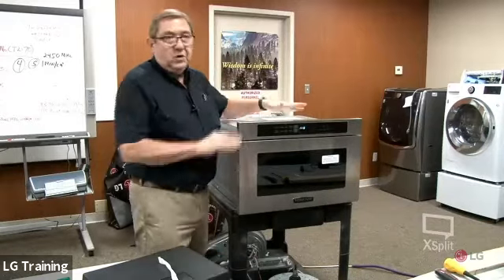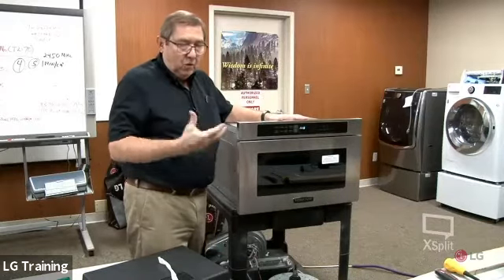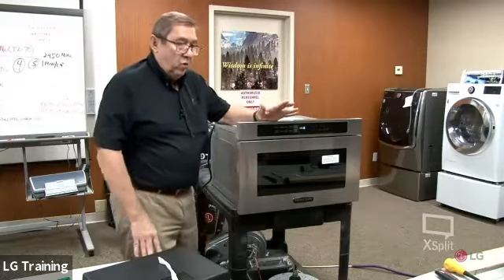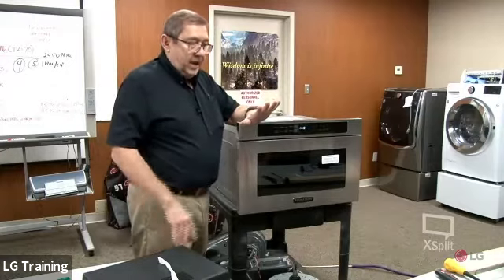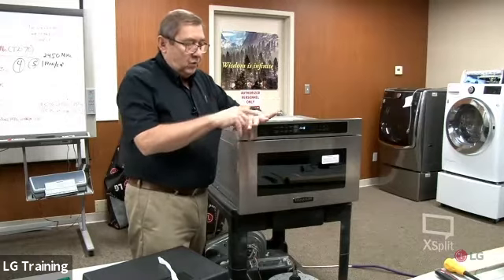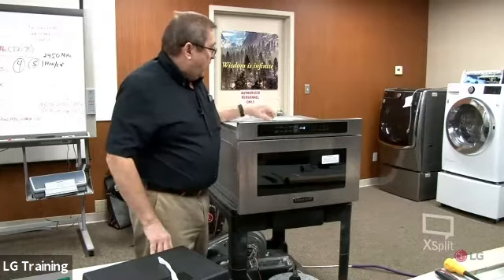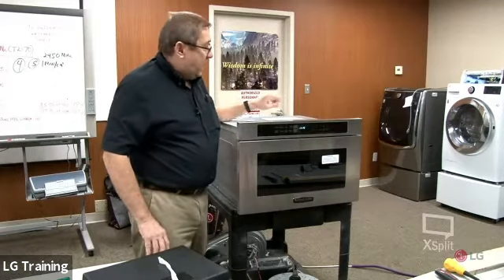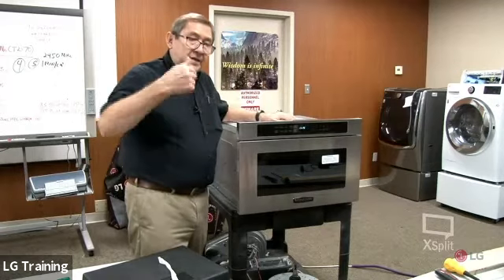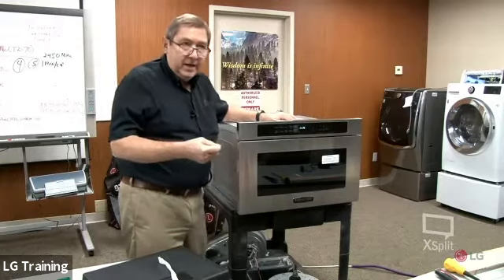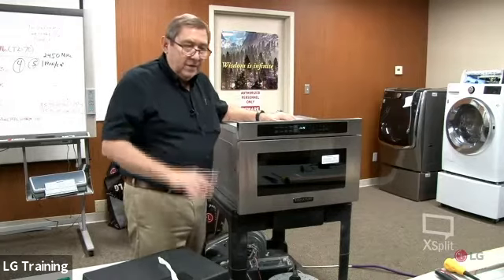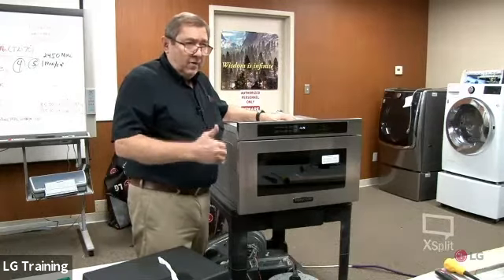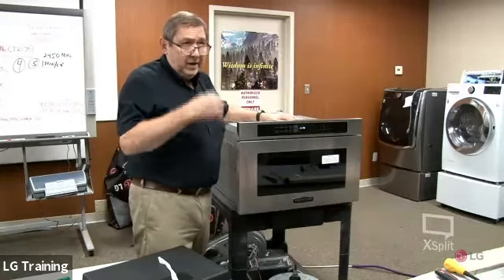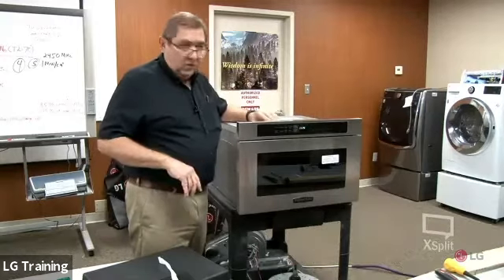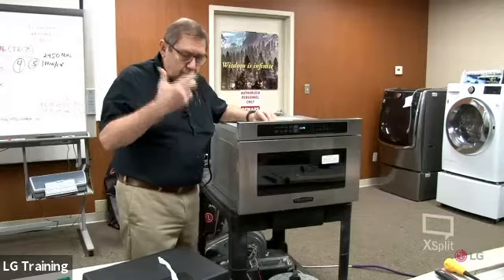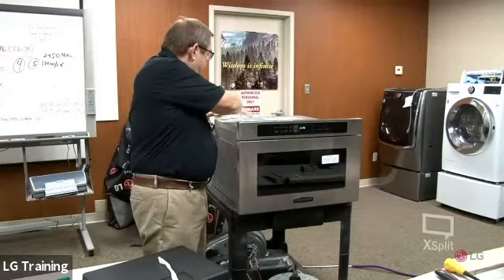We also have two boards in the back, and one of them is the power board. I kind of look at it as a relay board - there's four relays on there, marked RY1, 2, 3, and 4. Your R1 goes to the lamp assembly. R2 is the one that breaks, not the secondary, but the primary side of your high voltage transformer - that's how we get the different power levels. Then we have R3, I believe that one's for the turntable, and R4 - I might have them backwards - but the other one is for your blower, your cooling fan for your magnetron.